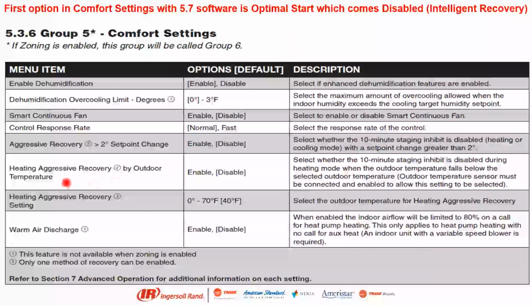We can actually set heating aggressive recovery for when it gets colder out. So we can set that at certain temperatures too. So we have a lot of control in there. Warm air discharge, when enabled, the indoor airflow will be limited to 80%. That just says it's going to start at a lower speed to let that coil get nice and warm.